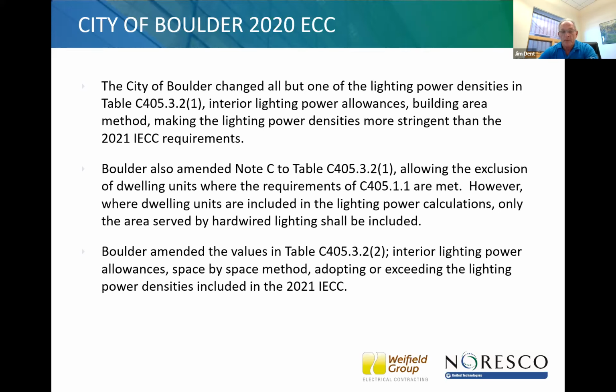So it's going to be more difficult, for example, in the additional energy efficiencies. One of the things you're able to do is to improve your lighting power density to be 10% better than code. In Boulder, that's going to be more difficult than in other jurisdictions, because their lighting power densities are considerably more stringent than the IECC.